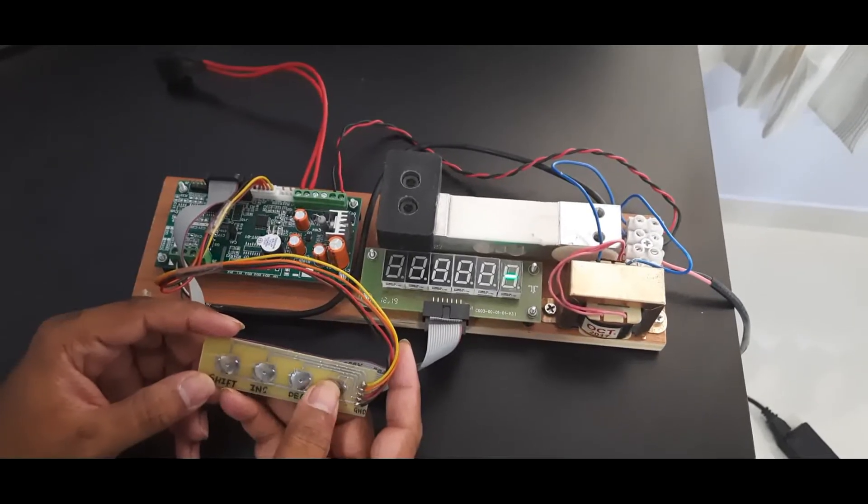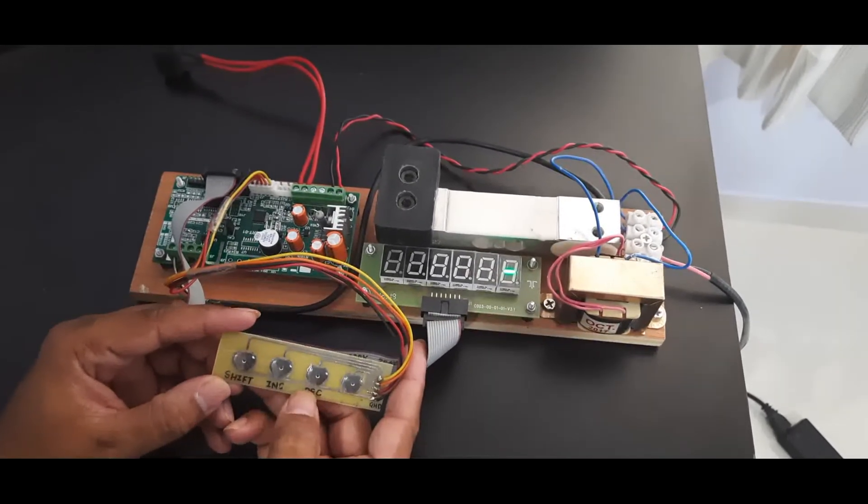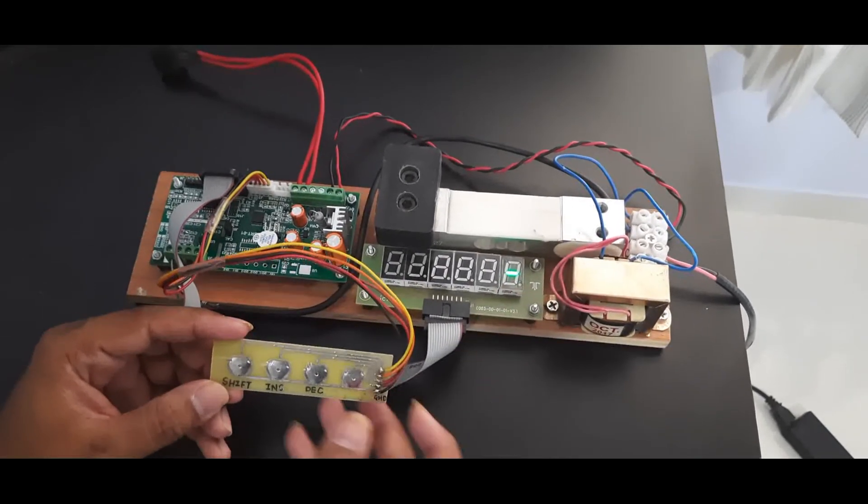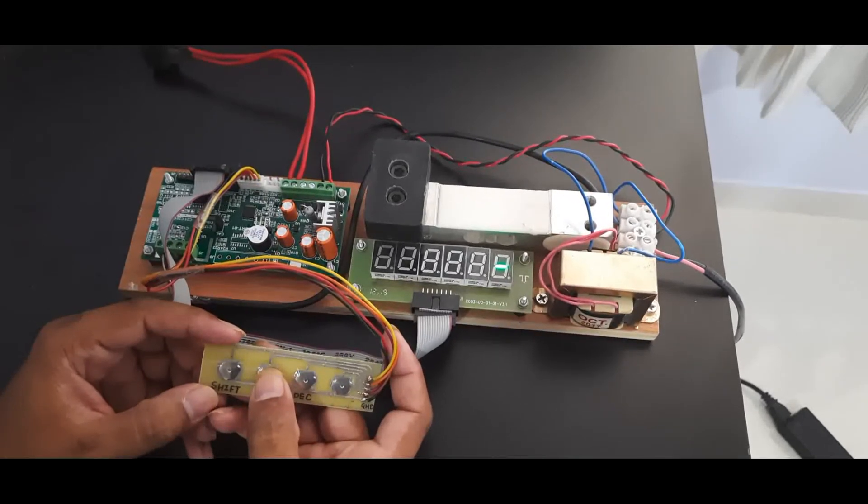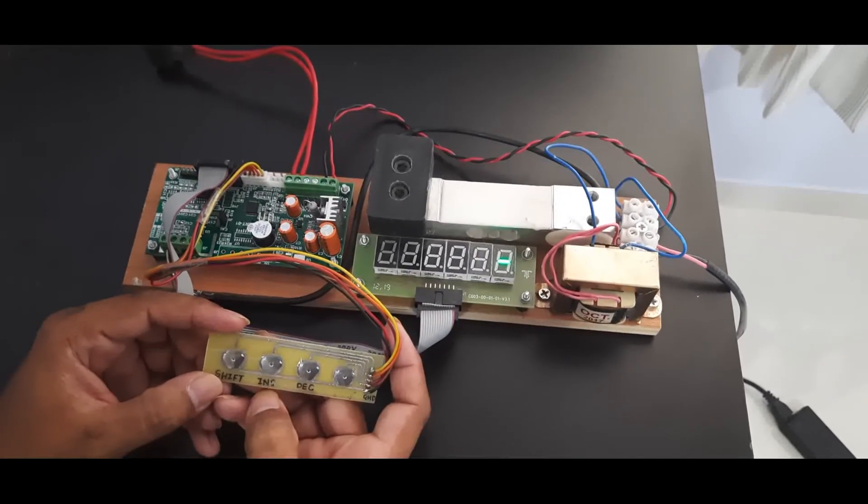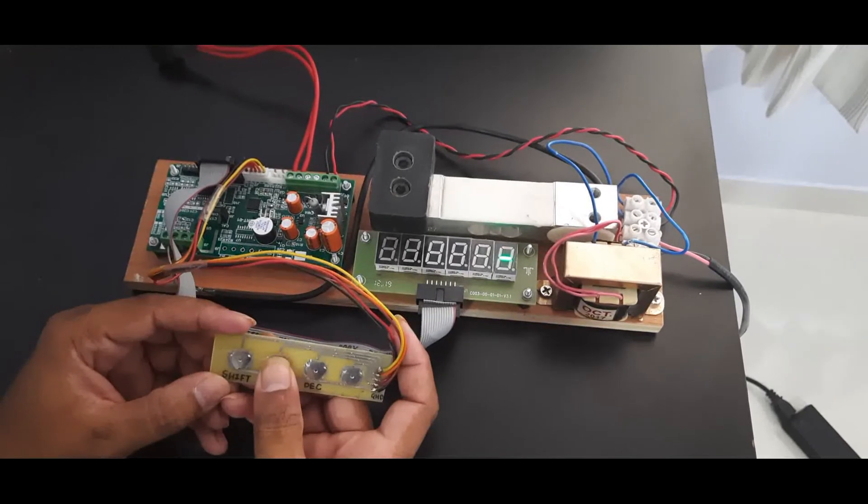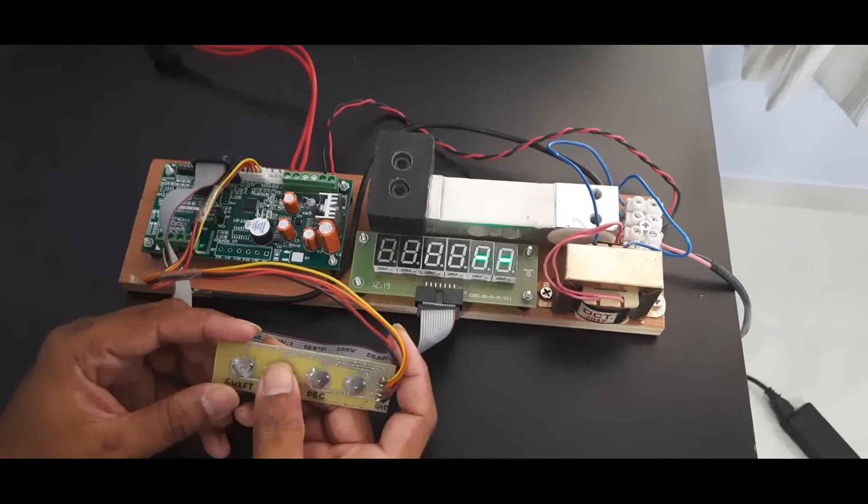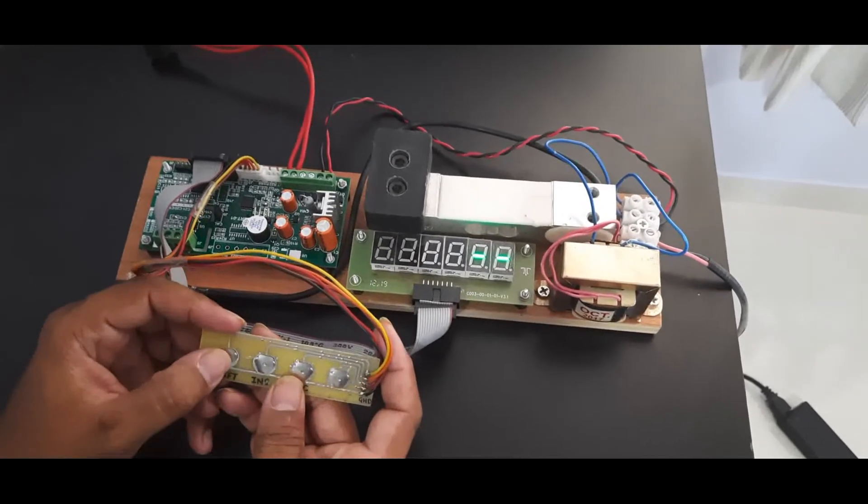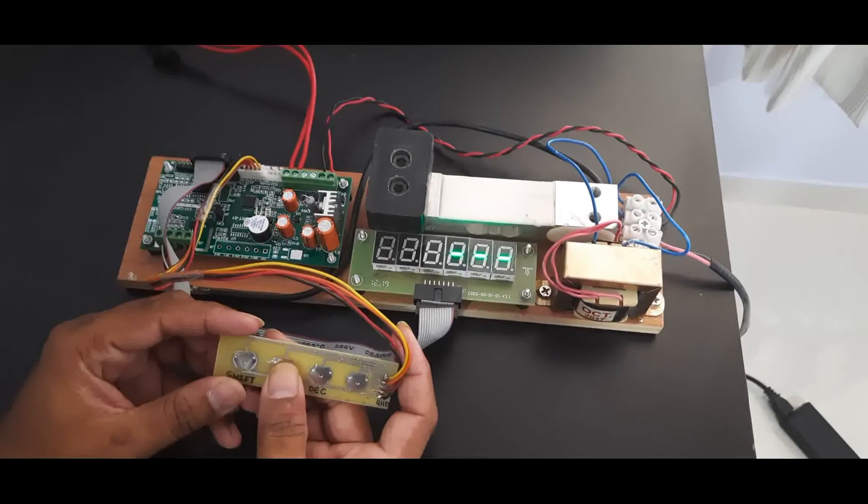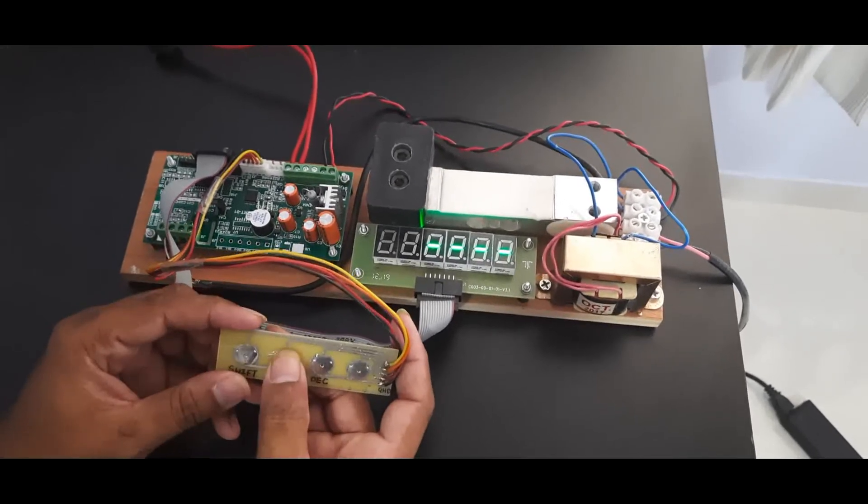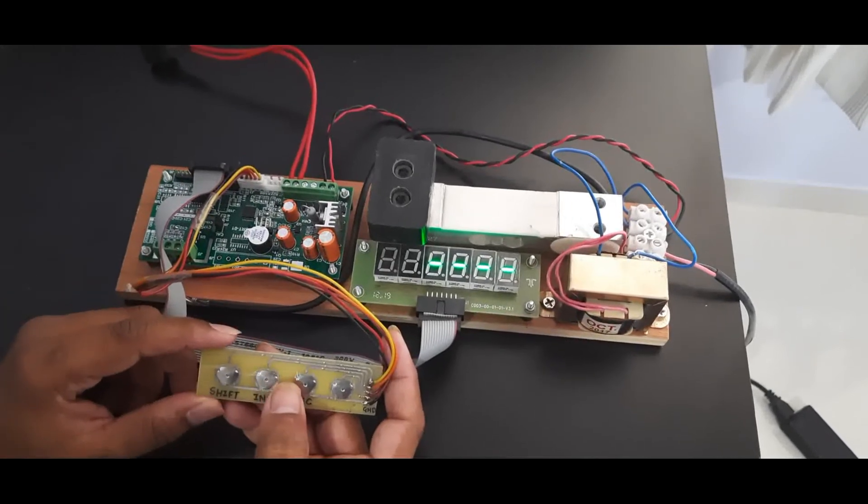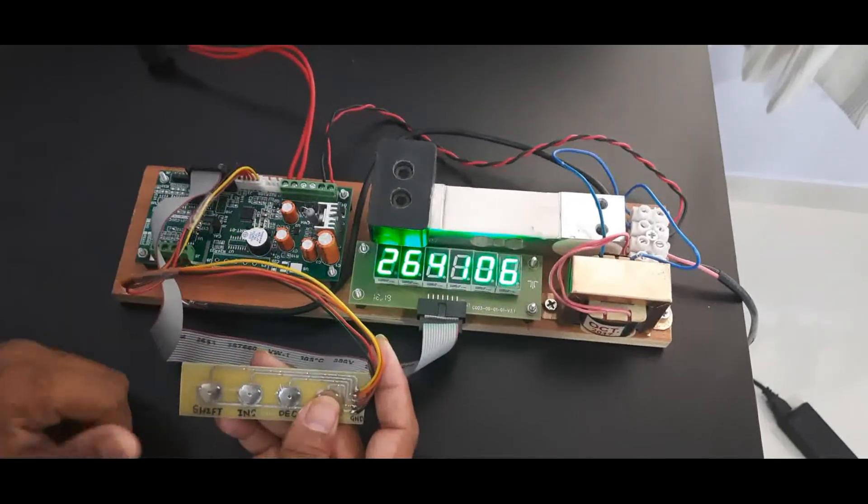Calibration password is four times two. By default the value of the hyphen is zero. To enter two, I need to press increment key twice: one, two, then shift. Again one, two, shift. Again one, two, shift. Again one, two. I've entered the complete password 2222. Now I press enter and it goes into the calibration menu.